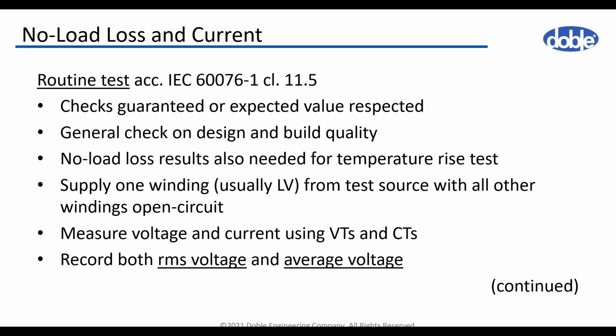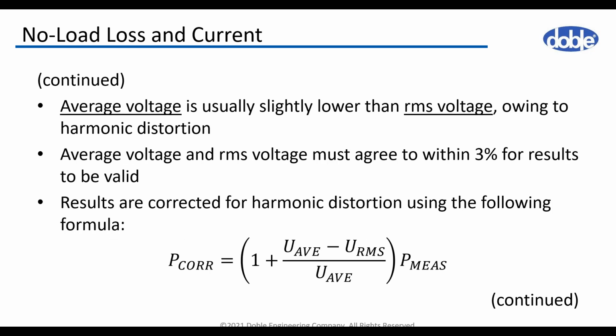Specific for this no load loss measurement is that the voltage on the unit under test is usually distorted, caused by the non-sinusoidal no load current of the test object, and both RMS and mean voltage should be measured. We can declare that the no load loss measurement is valid if the difference between RMS and mean voltage is less than 3%. To obtain a final test result, the measured no load loss is corrected using the formula which you can see at the bottom of the slide. It is very simple and very well defined in IEC 76 part 1.